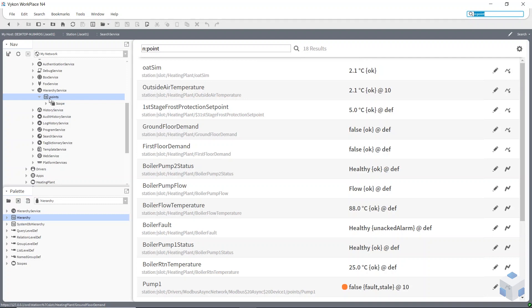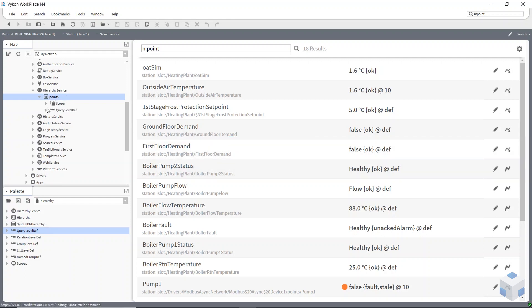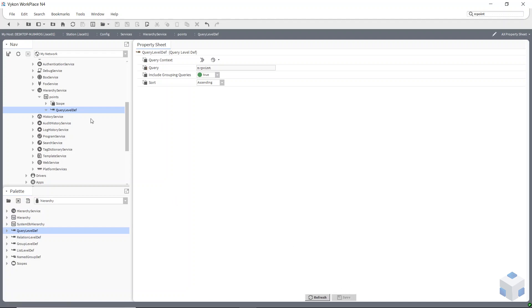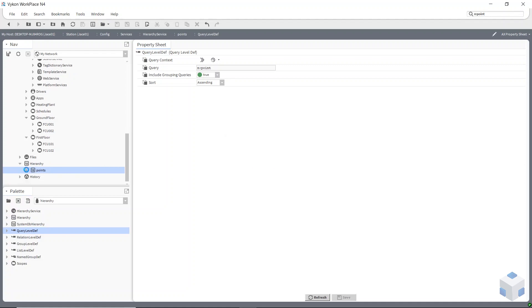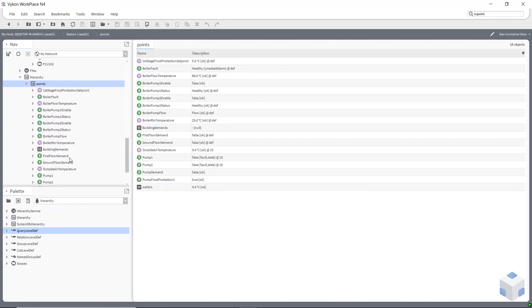This is the most basic type of hierarchy. I'm now going to add a query level definition to my point hierarchy, and in the query I'm just going to put n colon point. Every time you make a change to a hierarchy you have to right-click on it and refresh it — you do it on the hierarchy itself. Now it's worked — if I double-click on it it's a list of all my points on my station using that n colon point query.